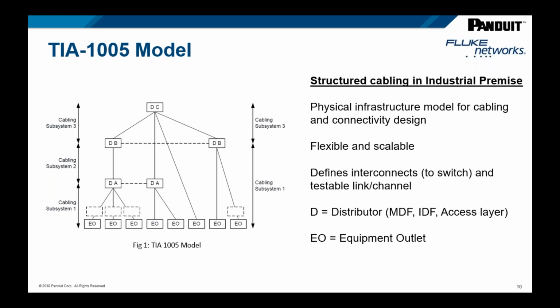From the bottom up, these are depicted as distributor A, distributor B, and distributor C. You may be most familiar with distributor C, the patch panels and patching co-located with the network core equipment in a telecom room, for example. The cabling subsystems also start at the bottom and move towards the network core, defining the structured cabling: the links connecting the equipment outlet are cabling subsystem 1, then moving up you have subsystem 2 and subsystem 3 attaching the network core.